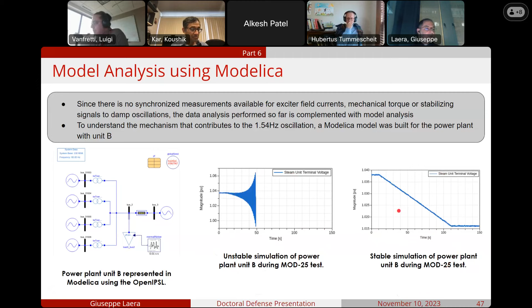The substation model has 3 gas units and a steam turbine. They are all connected to bus 2 through transformers. And a load is placed at bus 2, and it's also connected to a noise source in order to produce variations that are similar to ambient conditions. So after performing various simulations in the cloud using different loading conditions, it was verified that, depending on the loading conditions, some pairs of eigenvalues became unstable, as observed in the real data. And this is confirmed in the model as well, where we can see the unstable simulation here and a stable simulation here.